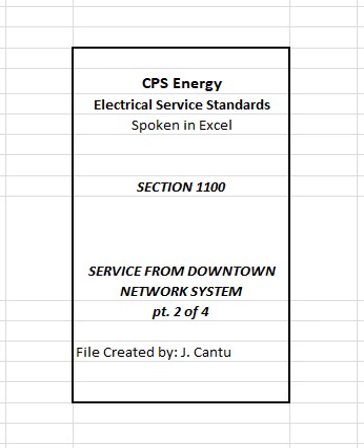Based on the customer's load, a standard CPS Energy transformer vault or room can normally accommodate up to 4 transformers. Floors shall have a smooth finish to allow for steel rolling rods to move freely. Note: where constructing a transformer room within an existing building, CPS Energy will require a structural engineer sealed letter attesting that the construction of such floors is adequate for the conditions and the imposed equipment weight to be supported.